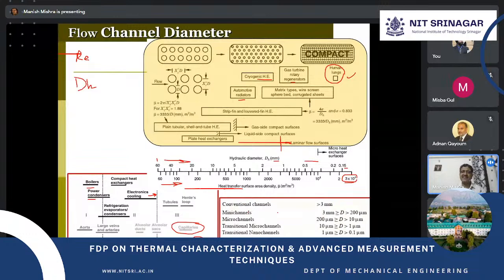Instead of dividing heat exchangers into simply two basic categories, compact and non-compact, we further divide them into conventional channels, mini channel, micro channel, and so on, even nano channels nowadays. This is the value of hydraulic diameter, and how it changes accordingly. You might have seen many applications of micro channels, mini channels, and so on, but what category a channel falls into is basically based on the hydraulic diameter. Once we calculate the hydraulic diameter, we define what category of channel it is. But apart from the definition of the channels, we are totally changing the flow behavior inside, and that ultimately gets reflected in heat transfer and the pressure drop phenomena, flow friction phenomena.